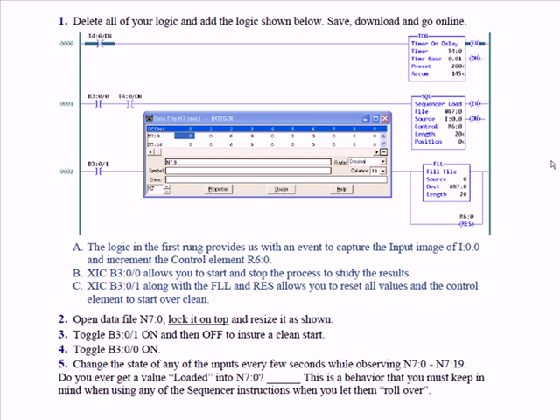So, open data file N7, lock it on top, and resize it as shown. Toggle B3:0/1 on, and then off to ensure a clean start. So you clear out your stack or your 20 registers for your sequencer load instruction. Then toggle B3:0/0 on.